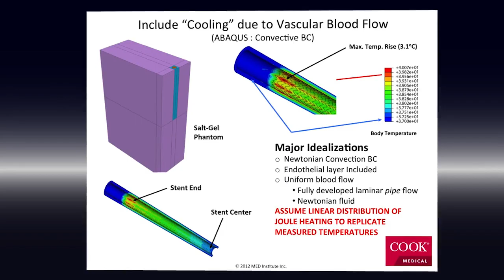Then I make a separate model of a vessel, assume a laminar pipe flow that's fully developed. We iterate on a Nusselt number that seems appropriate. Assume that flow goes through even with a healing endothelial layer, which will cover the stent as it heals in the vessel. And sure enough, with an approximation of blood flow going through, the temperature rise goes from 10 degrees to 3.1 degrees. Okay? Now we're convinced that, hey, the blood will cool this. It will not really see 10 degrees. That was an artifact of the test. And actually, this went through regulatory approval, and everybody's happy.